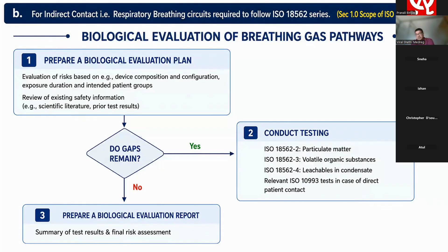If you are in this category, there are 4 sections in ISO 18562 required to be followed for indirect contact, mainly applicable to the breathing gas pathway. So when we refer to ISO 18562, part 1 is the general chapter, same as ISO 10993 part 1, whereas parts 2, 3 and 4 of ISO 18562 talk about conducting the different tests. In case of the breathing gas pathway, we must conduct tests for particulate matter, volatile organic substances, and leachables.